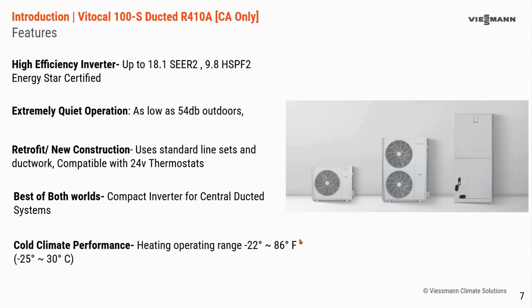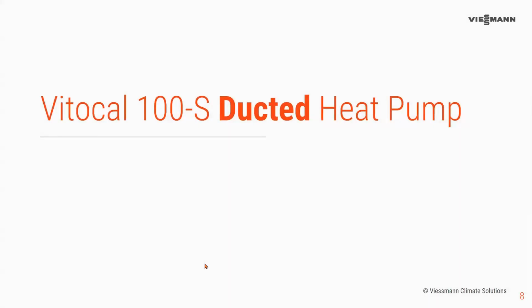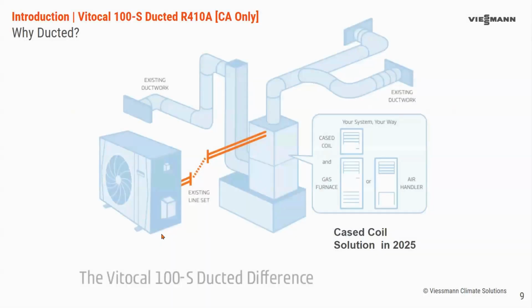And we'll talk a little bit more on the standard heat versus high heat, but we have a high heat and a standard heat option, but the range here is for the high heat down to negative 22 degrees Fahrenheit, negative, I believe that should be negative 30 C, but we'll correct that. So the Vitocal 100S ducted heat pump.